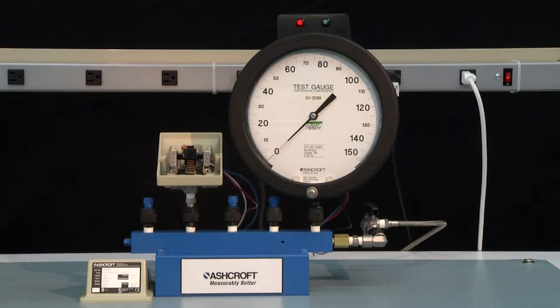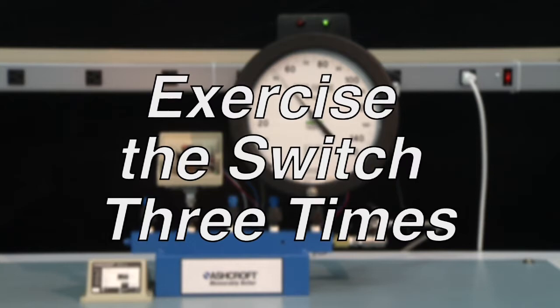The first step of calibration is to exercise the switch to make sure it is operating correctly. To exercise a switch, start from 0 PSI and increase to full range of the switch. In this case, 100 PSI and then return back to 0. This should be done three times.